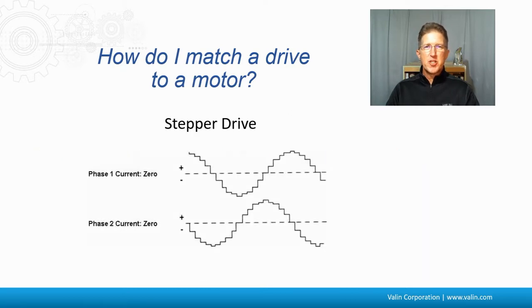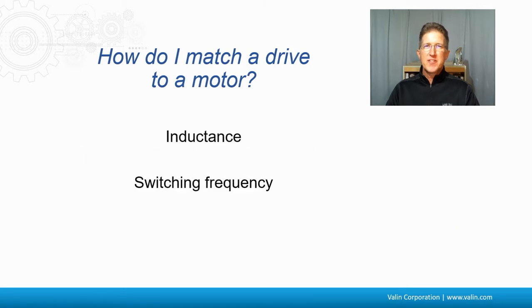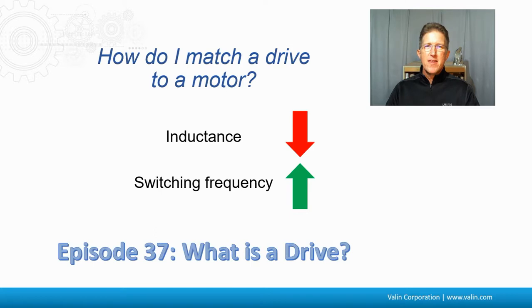Then there are stepper drives, which just index through known positions — that's in episode 41. There are a couple of things I don't touch on enough, and that's inductance and switching frequency. When the inductance of the motor goes down, the switching frequency needs to go up in the drive in order to control the current well. That's episode 37 — 'what is a drive?' — I do touch base on that. It's something that needs to be looked at when matching a drive and a motor together.